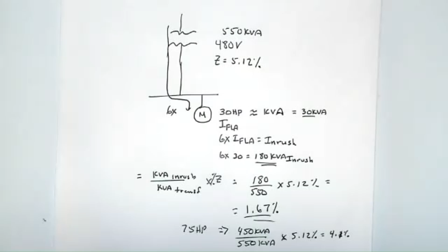So again, in summary, the motor is going to give us about 6 times inrush current. So once we create 600% full load amps for that motor, we had about 180 kVA of inrush kVA, and then we ended up with about 1.67% drop. So for that percent drop, we don't really need or require formal analysis, and we should be good in this situation. Then if we repeat that, 75 horsepower, 75 kVA times 6 gives us about 450 kVA of inrush divided by the transformer kVA times the impedance of the transformer, which gives us about 4.1% voltage drop.